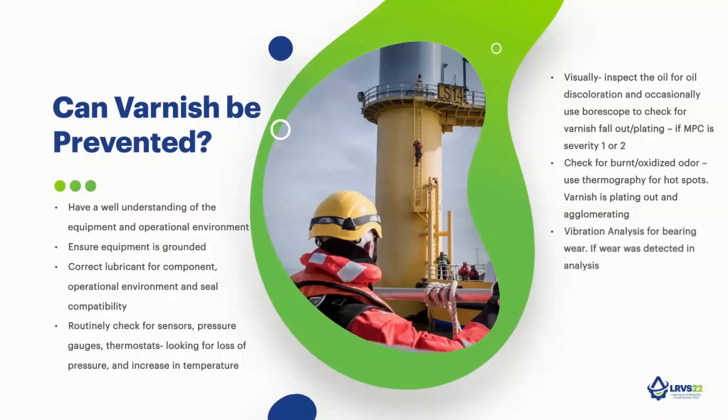Vibration analysis is also a key analysis or field testing to do to check for any bearing wear, misalignment that might be going on, or if a bearing is failing. And lastly, a filtration system that is applicable for the system, but also for the operational environment as well.